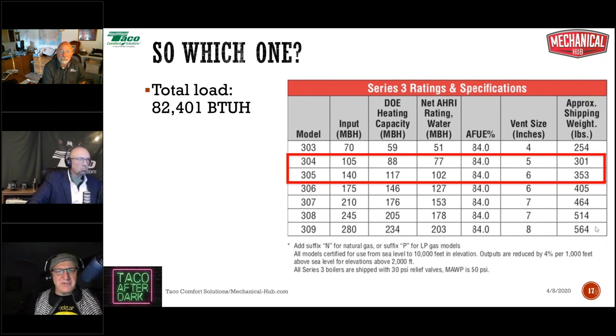You can play a shell game with the BTUs and that works just fine. It's just that if there is ever an instance where the homeowner wants all of the zones calling at the same time, no, that's not going to work. You're not going to have that. So you got to know your customers pretty well, and they got to know you pretty well. You may reach a point where, okay, it's really cold out, and I want this zone all warm, and it doesn't work. You're asking for a little bit of interaction. But if it works for you and works for your customers, by golly, you're going to make sure that boiler's maximum in terms of efficiency, which is pretty cool.